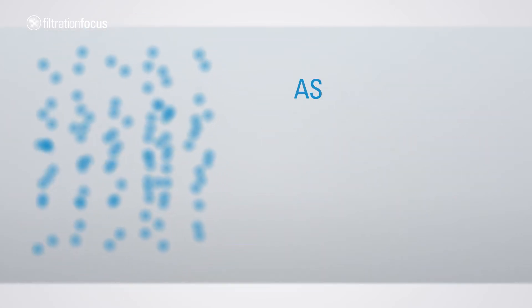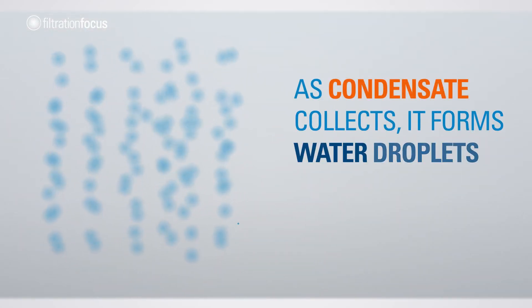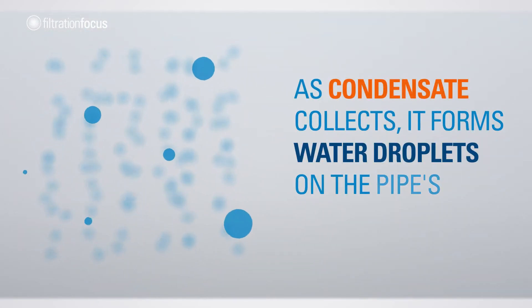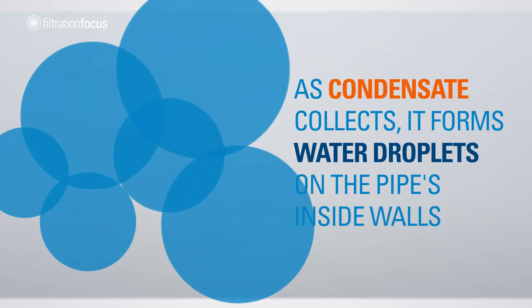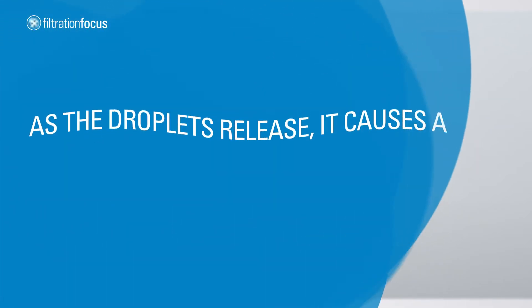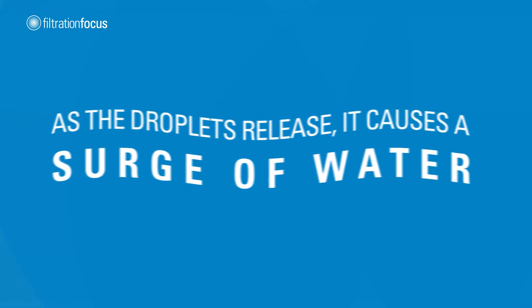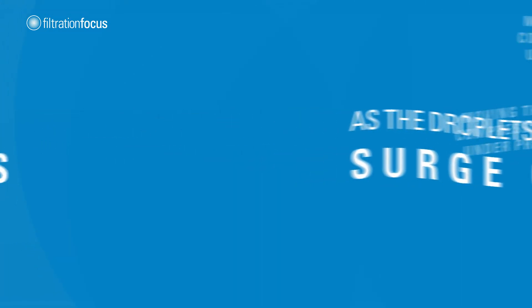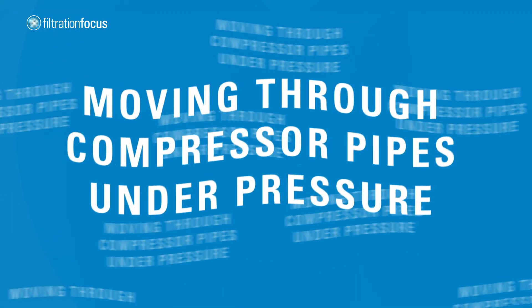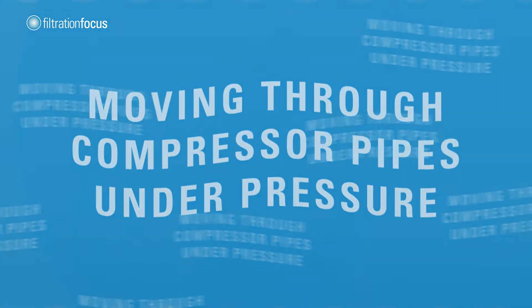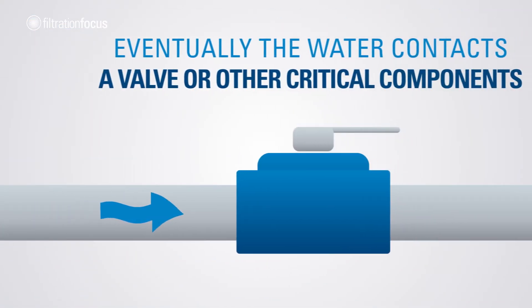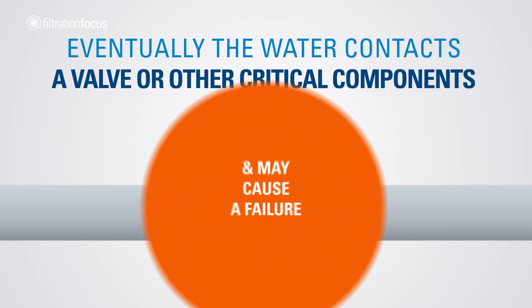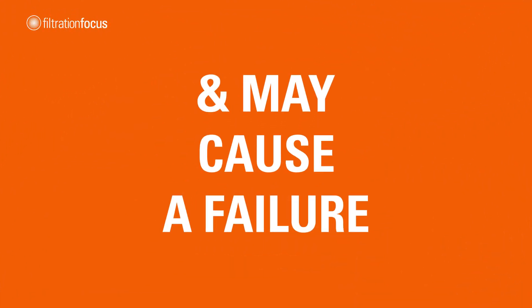As condensate collects, it forms water droplets on the pipes' inside walls. As the droplets release, it causes a surge of water moving through compressor pipes under pressure. Eventually, the water contacts a valve or other critical components and may cause a failure.